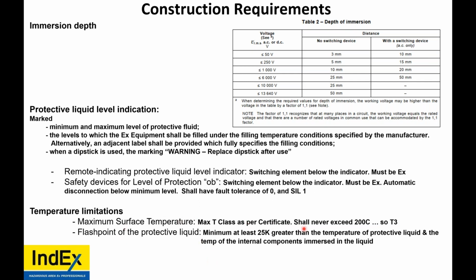So the maximum surface temperature shall not exceed 200 Celsius. The flash point of the protective liquid must be a minimum 25 K greater than the exposed protective liquid or the temperature of the internal components immersed in the liquid. Yes, so the IEC standard for SIL ratings, IEC 61508, and also consider 61511.